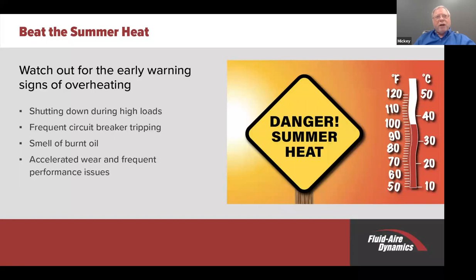Early warning signs—shutting down. If your compressor shuts down, there's obviously an issue. Typically it shuts down because of high temperature, low oil levels, and other reasons. So if you have a shutdown, don't ignore it. Find out the cause. It could be anything from basically the cooler being dirty, low oil levels in the machine, or the fact that the oil has been running for such a long period of time at high temperatures that you've varnished not only the cooler, but the compressor itself.